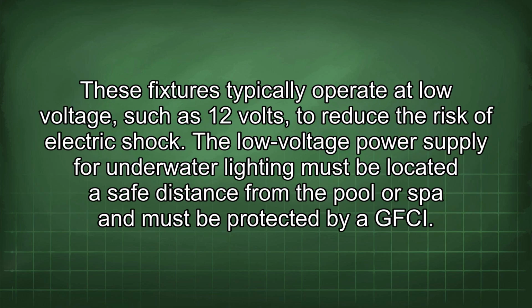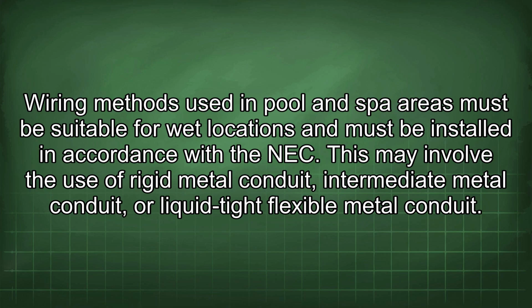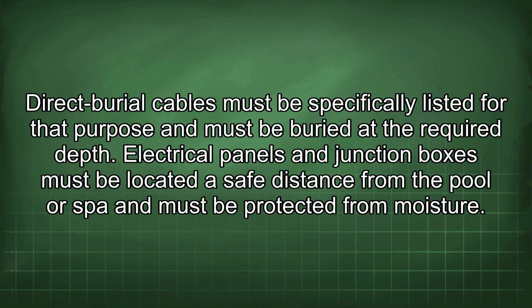These fixtures typically operate at low voltage, such as 12 volts, to reduce the risk of electric shock. The low voltage power supply for underwater lighting must be located a safe distance from the pool or spa and must be protected by a GFCI. Wiring methods used in pool and spa areas must be suitable for wet locations and must be installed in accordance with the NEC. This may involve the use of rigid metal conduit, intermediate metal conduit, or liquid-tight flexible metal conduit. Direct burial cables must be specifically listed for that purpose and must be buried at the required depth.